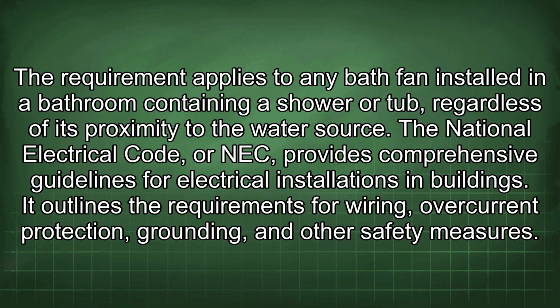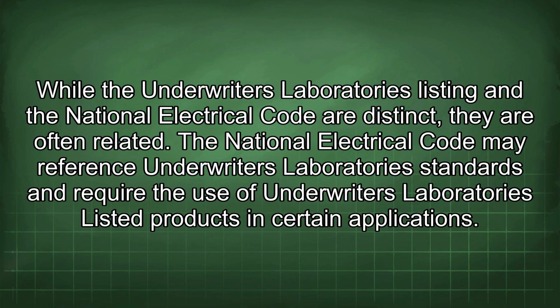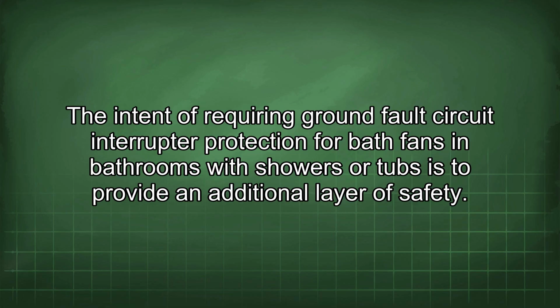to the water source. The National Electrical Code, or NEC, provides comprehensive guidelines for electrical installations in buildings. It outlines the requirements for wiring, overcurrent protection, grounding, and other safety measures. While the Underwriters Laboratories listing and the National Electrical Code are distinct, they are often related. The National Electrical Code may reference Underwriters Laboratories standards and require the use of Underwriters Laboratories listed products in certain applications. The intent of requiring ground fault circuit interrupter protection for bath fans in bathrooms with showers or tubs is to provide an additional layer of safety.